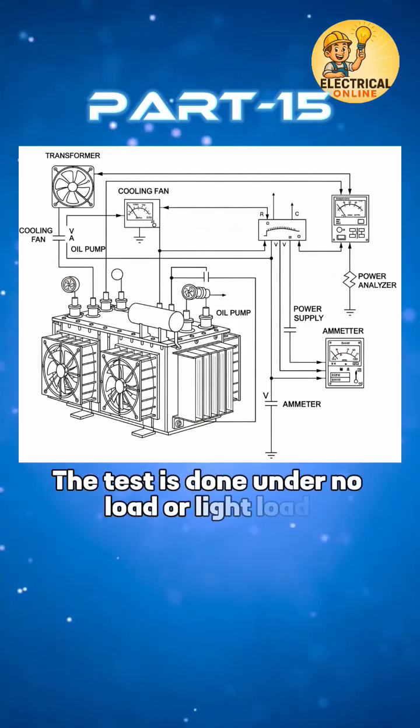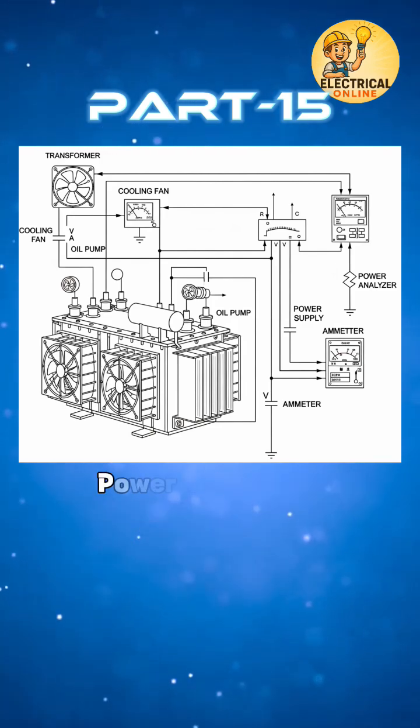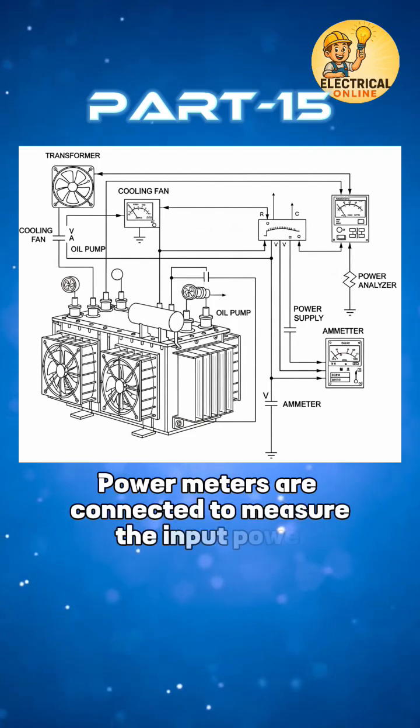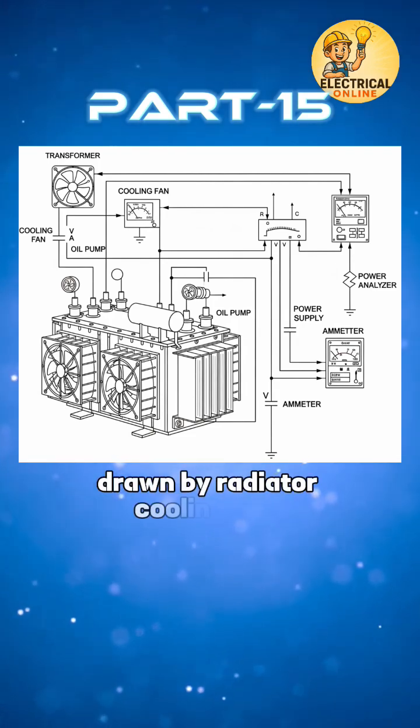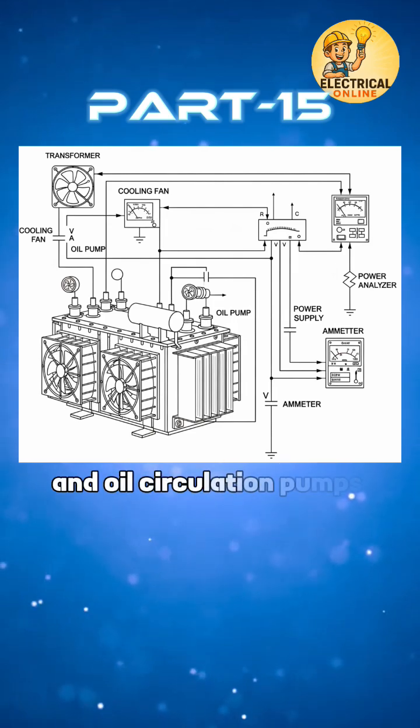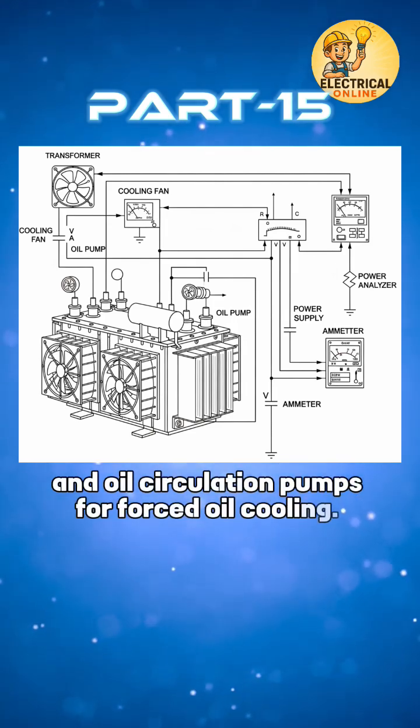The test is done under no load or light load conditions. Power meters are connected to measure the input power, in kilowatts or watts, drawn by radiator cooling fans and oil circulation pumps for forced oil cooling.